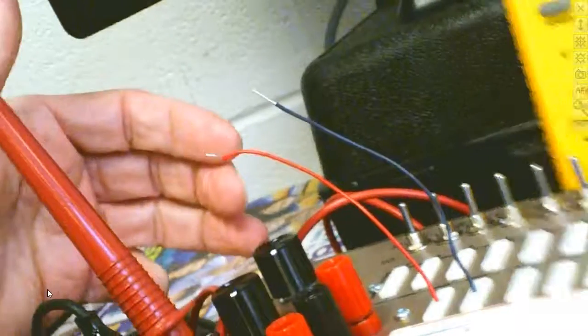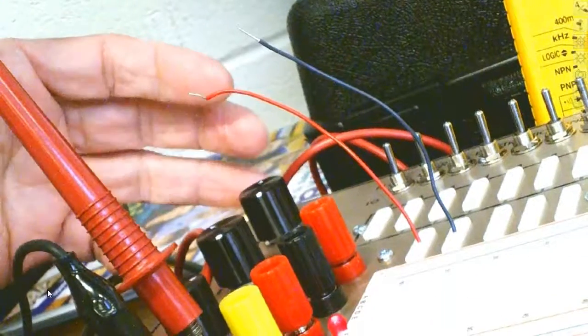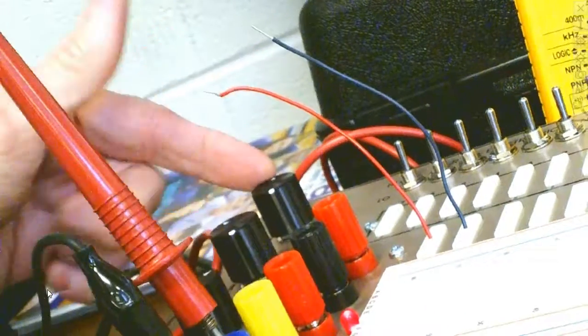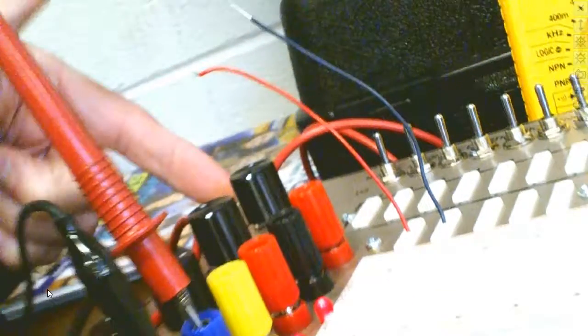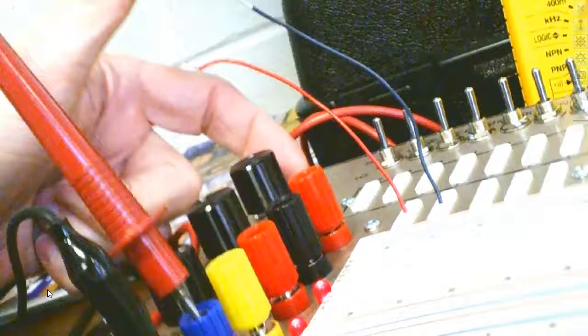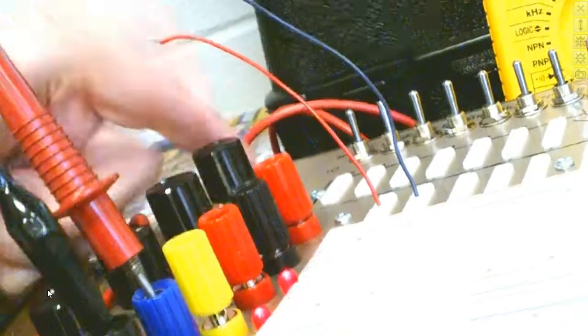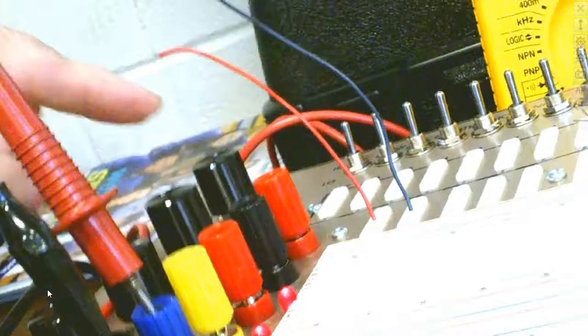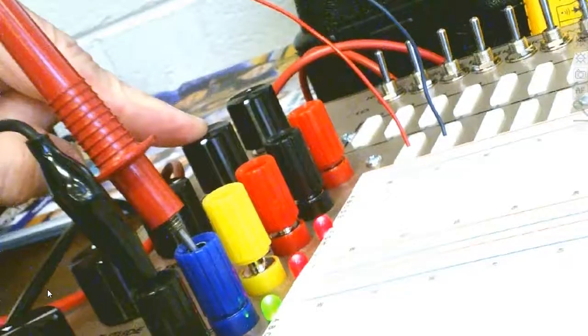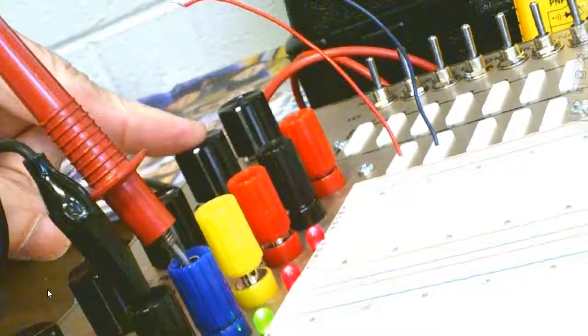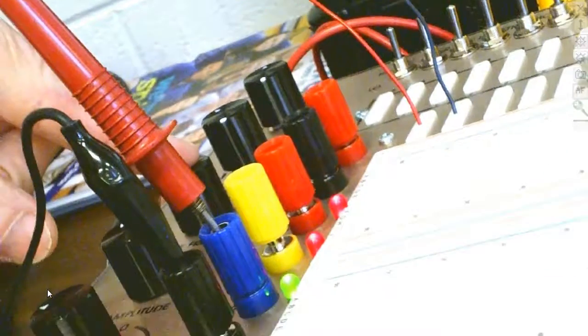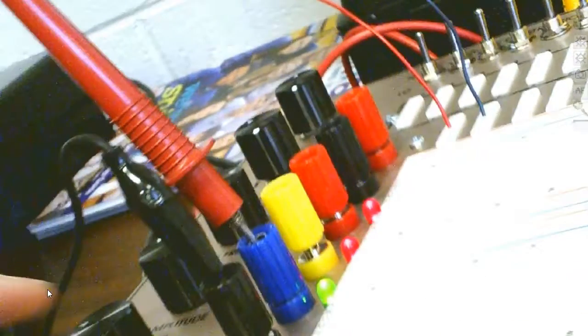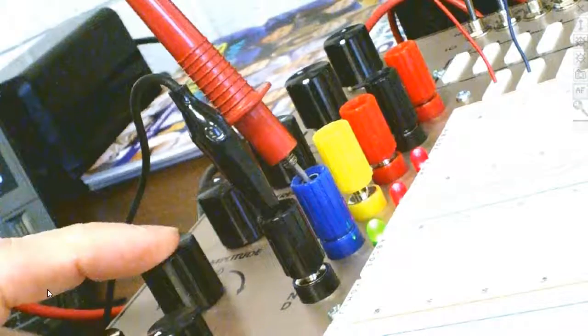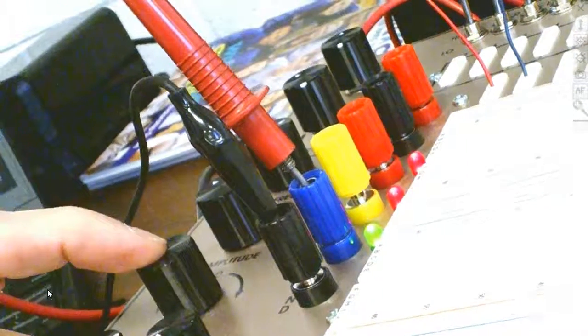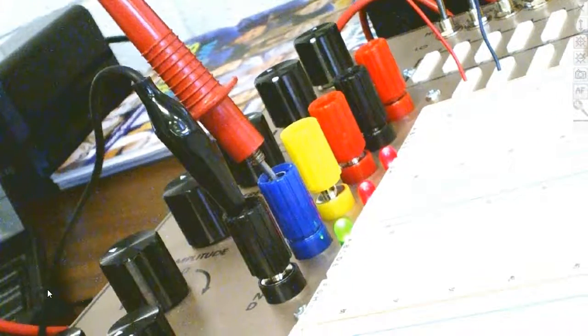We also have some electronics on it that we're not getting into. So we do have a function generator on it where you can select a sine wave, a triangle wave, or a pulse waveform with this knob right here. This is where you set the multiplier on your frequency. This is where you do a coarse adjust on your frequency output. This is a fine adjust, and this is the offset here. So you still have the ability to do an offset like we do in our function generator.